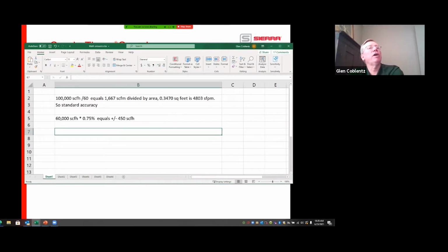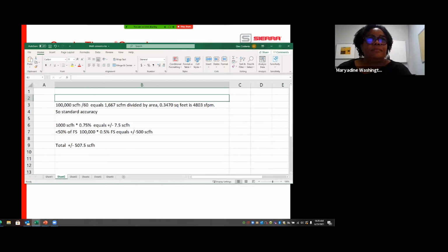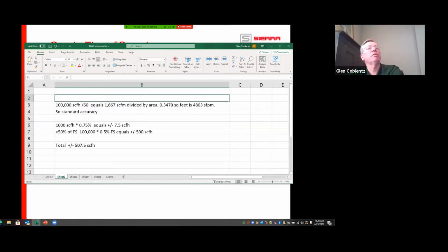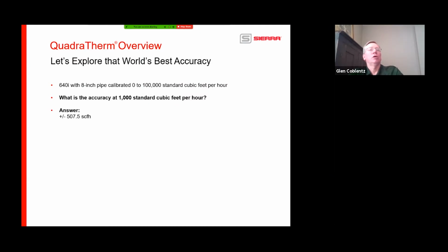Again, we're taking the 100,000, we're figuring out where we're at by the area. 100,000 divided by 60 SCFM, we get the standard feet per minute. But if we look, we're dealing with 1,000 standard cubic feet per hour. So it's 0.75% of reading equals this, but since it's below 50% of the calibrated full scale, you're adding a 0.5% of full scale, which is this. So that ends up being your total answer. And again, you can use that accuracy statement to determine the uncertainty at any point between 0 and the calibrated full scale.